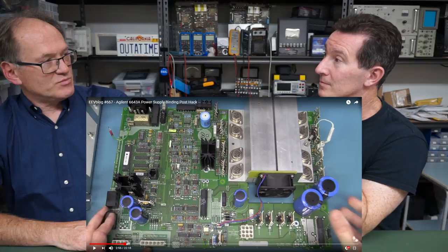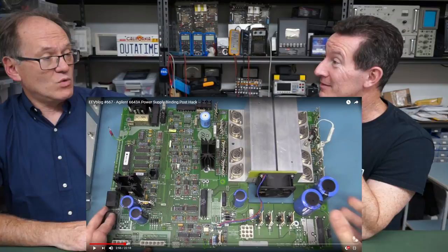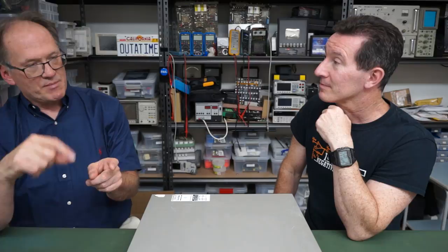It's a problem that's never going to go away, really, is it? It goes away by doing more modularization, and when you do modularization and you put things in the right groupings, we've made some relatively foolish mistakes in some of our products. We've grouped things that shouldn't have been grouped together. So, for example, this product was a good example. This product, the A to Ds and D to As are on the same board with the power supply. So that means we have five different versions of this board. So when that A to D changes, we have to build. So what we've done in the newer products is all the digital control is on a little plug-in board besides the memory module, and that snaps in. And then we actually use that to upgrade the performance of the product. We have different versions, but also when that part goes obsolete, that board is common to all the family. So we only have to do it once, and then we just pop it in and do the retest. So making some smart decision about partitioning helps the part obsolescence quite a bit, but sometimes it's just bad.